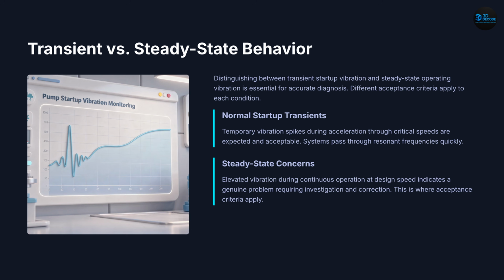Slide 14. Transient vs. steady state. Startup vibration spikes are normal, but high vibration during steady operation indicates a problem. Only steady state values are used for acceptance.